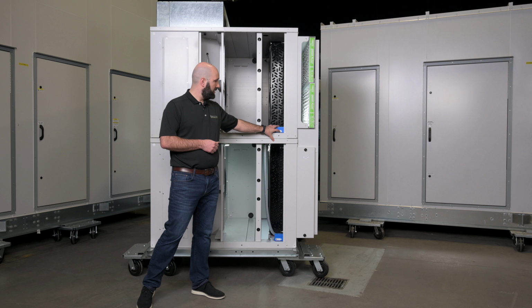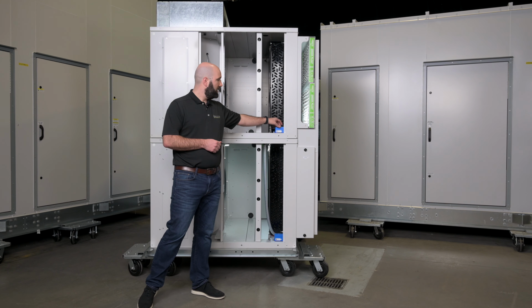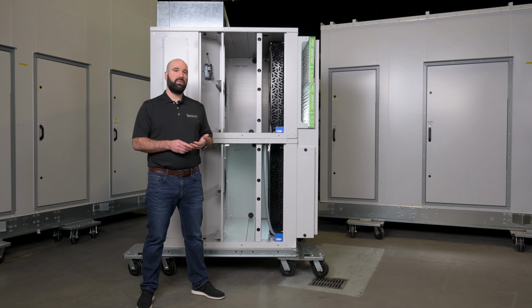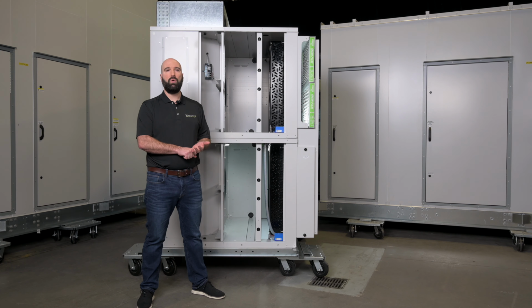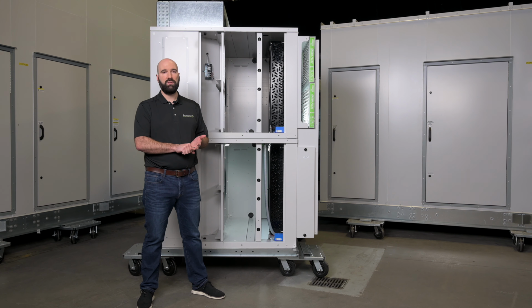This blue box here is an evaporator bypass damper controller, and using this actuator here, we're able to modulate the amount of air going through the evaporator coil, and it provides a couple of things for us. It allows us to increase the airflow through the coil when you're late in your cycle and you're running your room cold and dry, keeping our suction temperatures up and ensuring that you've got continuous performance from the system.